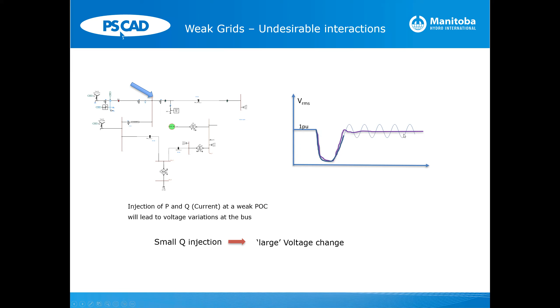So the weak grid is an indication of how meshed your system is, okay? And the second point I'd like you to take away from this is that a small injection of P or Q at a weak point of connection will lead to a very large variation of voltage at the bus, okay? This just essentially illustrates what I just mentioned. When you inject a very small current into the weak point, what you'll find is the system has sustained oscillations.